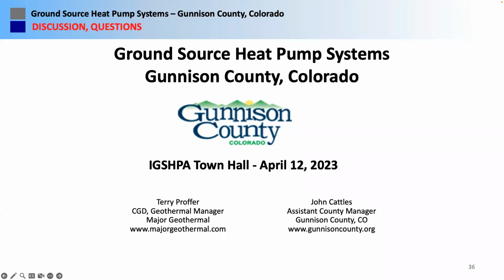I just know that the library has never got below 42 degrees supply water temperature, even though we designed the field for a minimum of 35 degrees. We did have a few more boreholes for safety factor, so that helps. Yeah. Most of the projects that I'm aware of, I've been involved with, were running plus or minus 40 degrees in the first case. Yeah, that's been our experience.